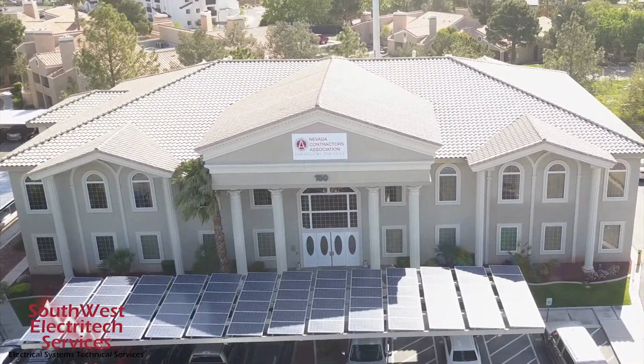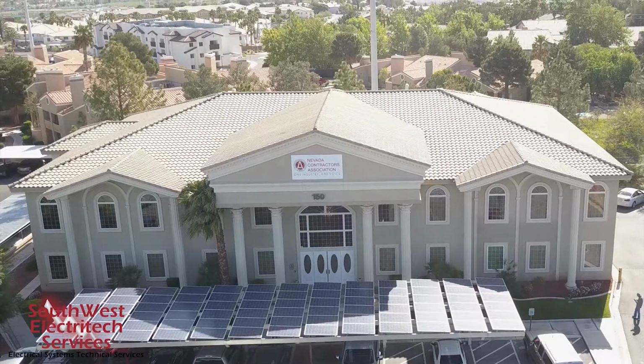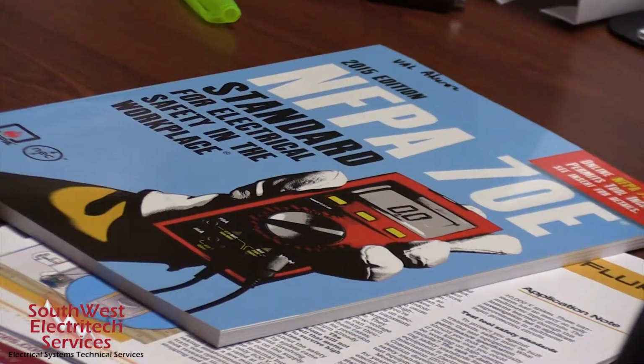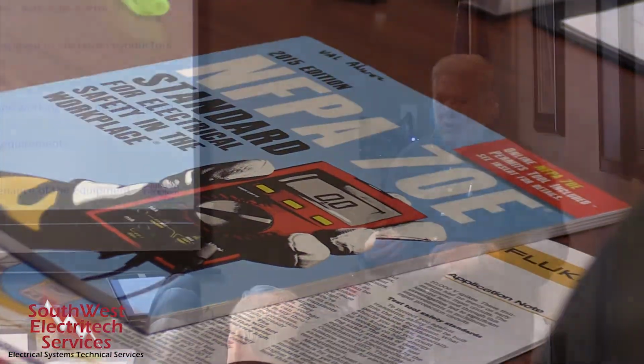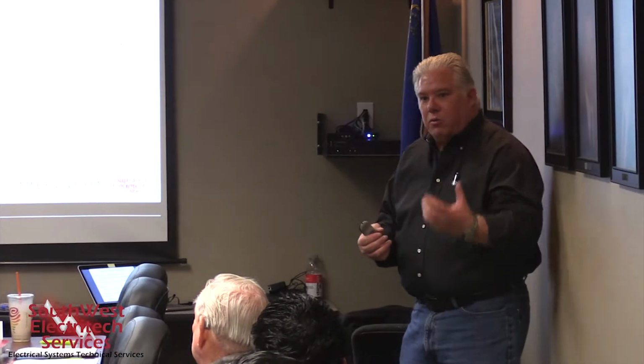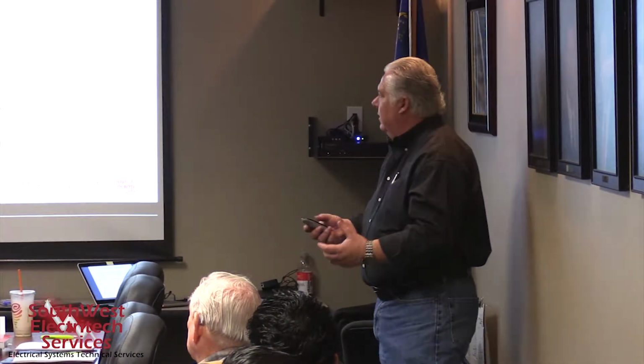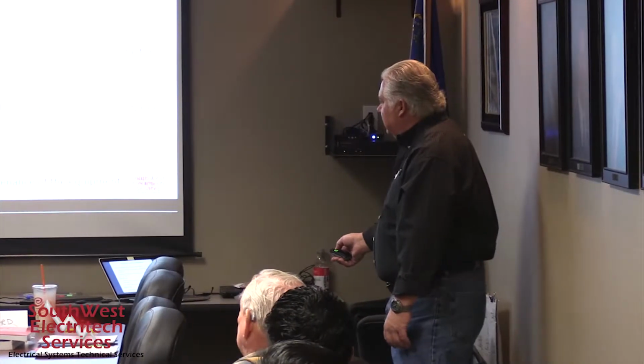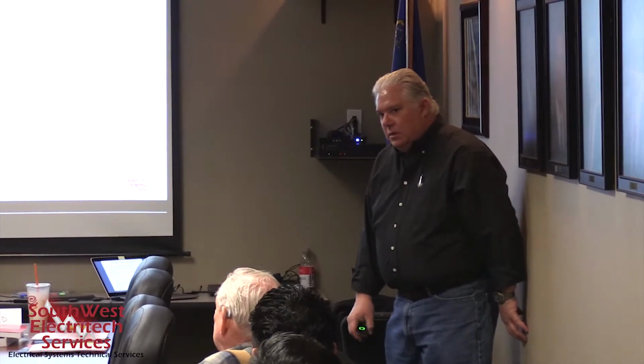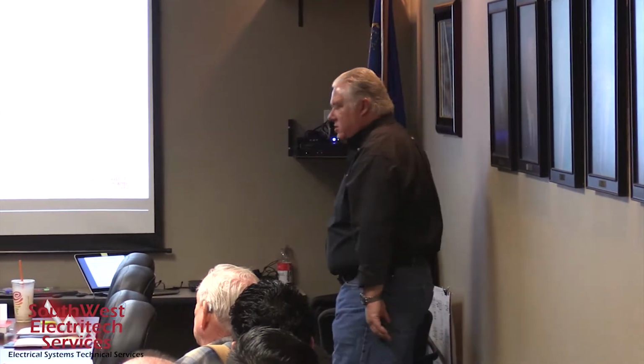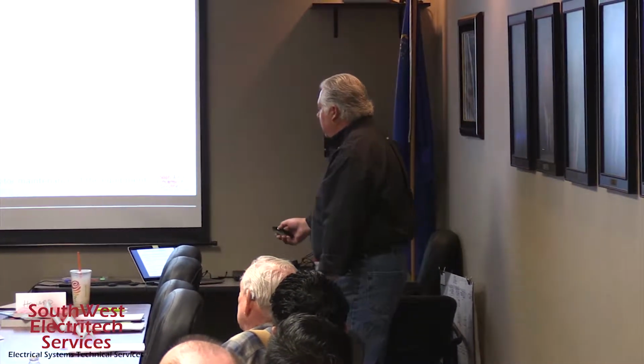NFPA 70E gives us the guidelines when we're working on or near energized equipment, when we're having to take that panel cover off and inspect something, or put a meter on and verify something. That gives us the guidelines for that. Keep in mind that 70E does not contain installation requirements. It refers you back to NFPA 70, which is the National Electric Code.